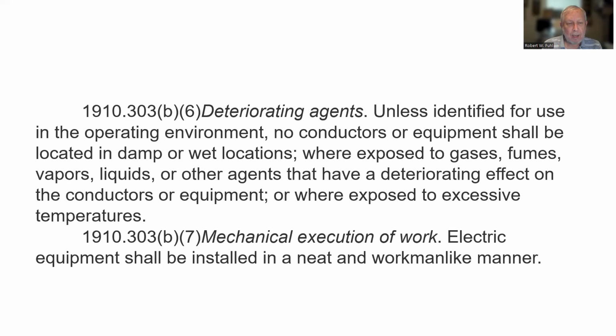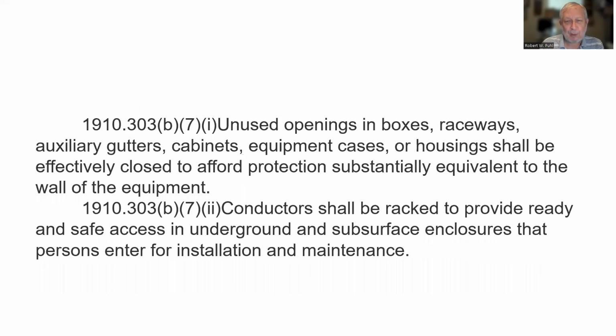Mechanical execution of work. Electric equipment shall be installed in a neat and workmanlike manner. If you've ever seen electrical equipment installed by a professional, you'll know what that means. Boy, it really looks sharp. They run the conduit inside, everything else. My son-in-law works as an electrician, and he sometimes takes pictures of stuff he's finished, and it's beautiful. It's a work of art. Unused openings in boxes, raceways, auxiliary gutters, cabinets, equipment cases, or housings shall be effectively closed to afford protection substantially equivalent to the wall of the equipment.